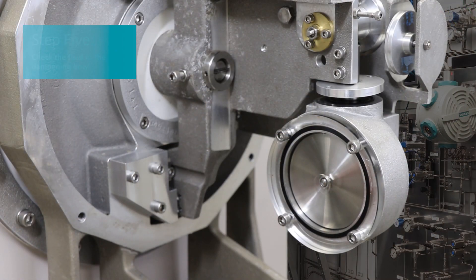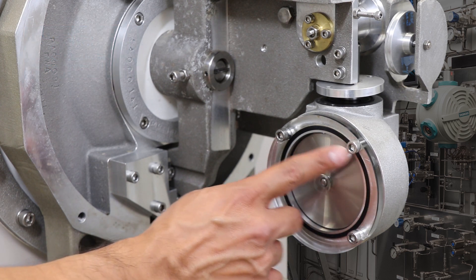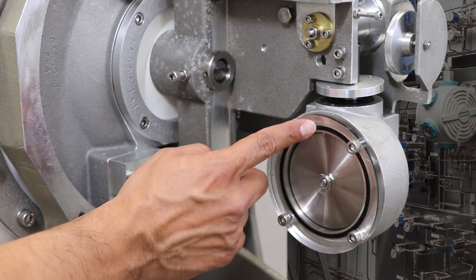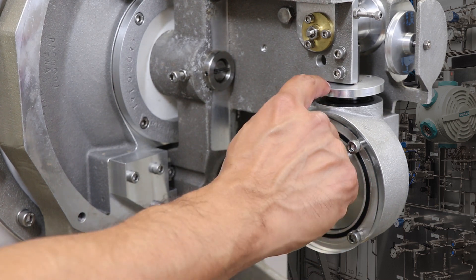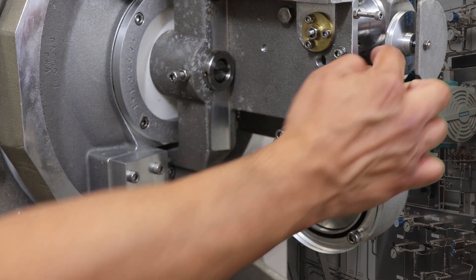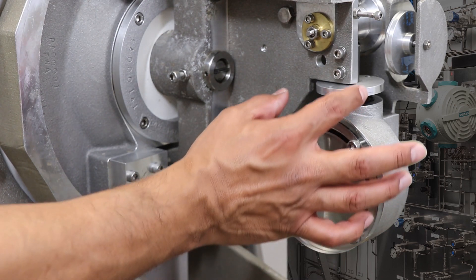Next we're going to check the fluid in the dampening bowl. When inspecting, make sure that the dampening bowl is 100% full with no bubbles. Please note that the fluid is clear in color. Also make sure that the two shipping bolts are removed from the dampening bowl disc. After you remove the two shipping bolts, make sure the aluminum disc is in the up position.